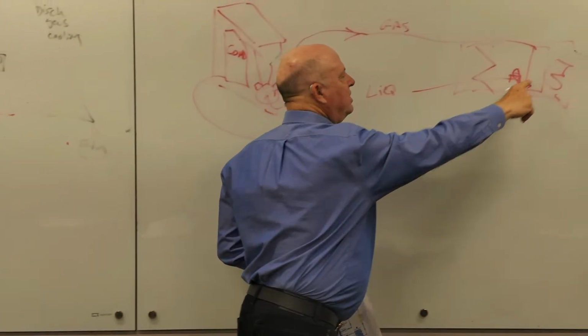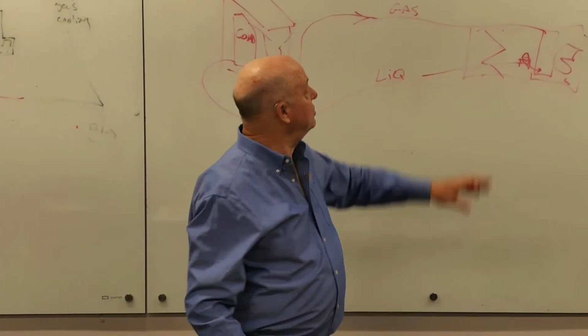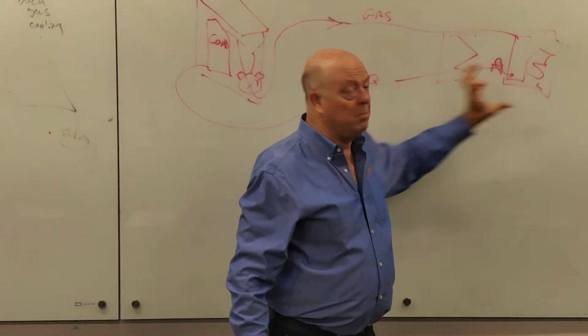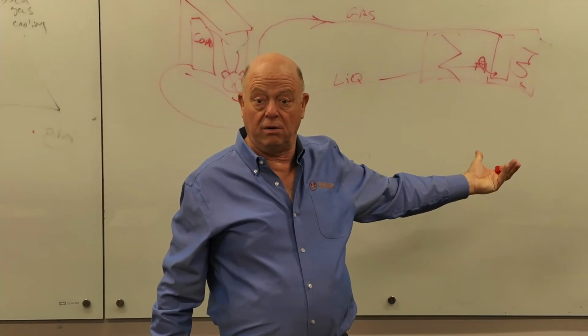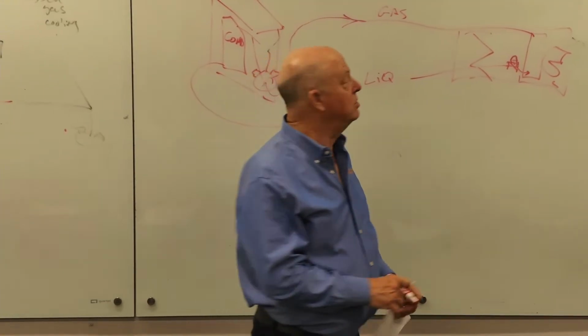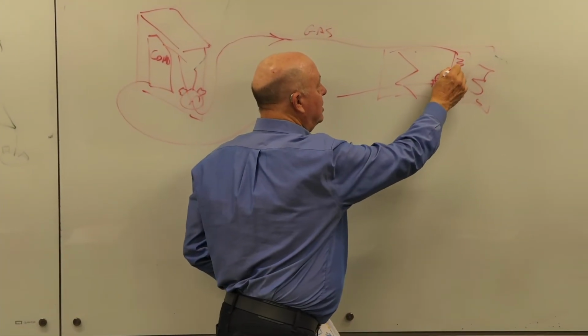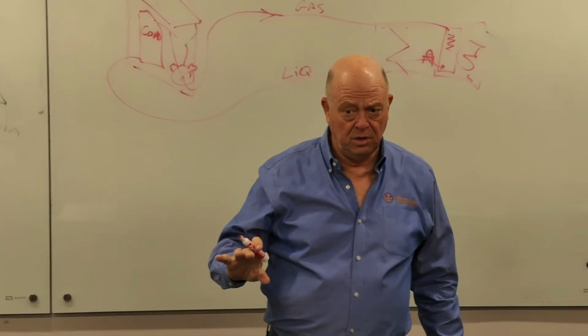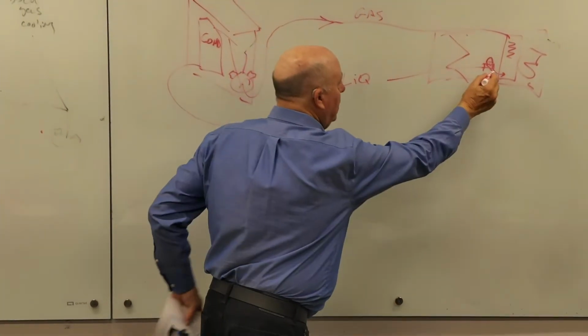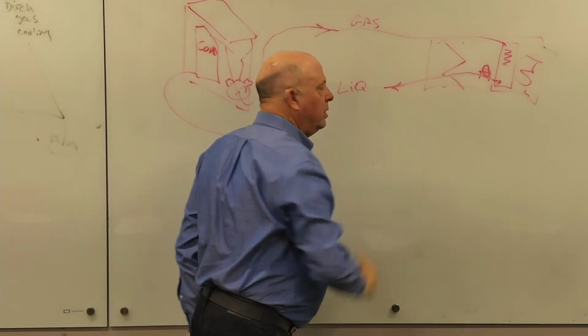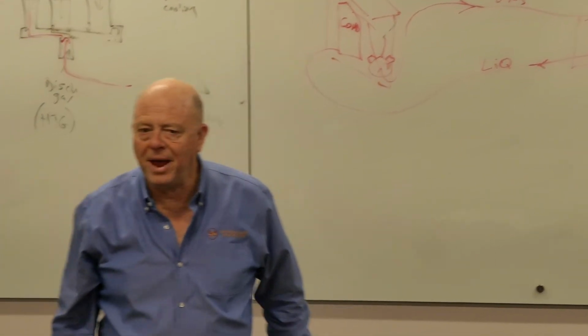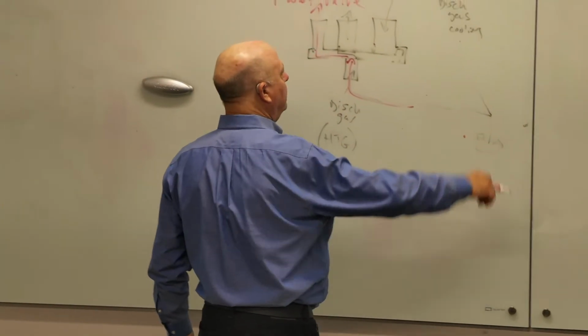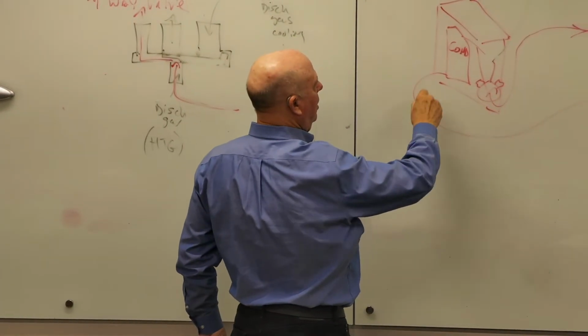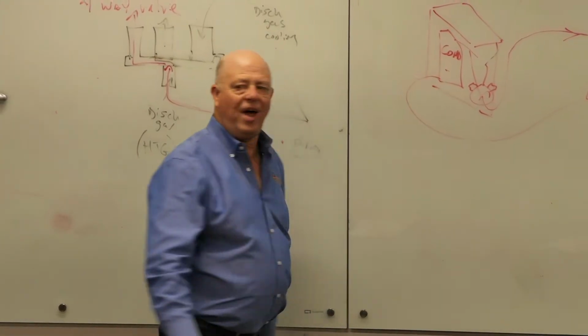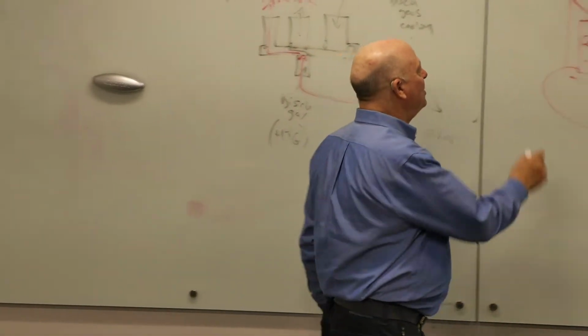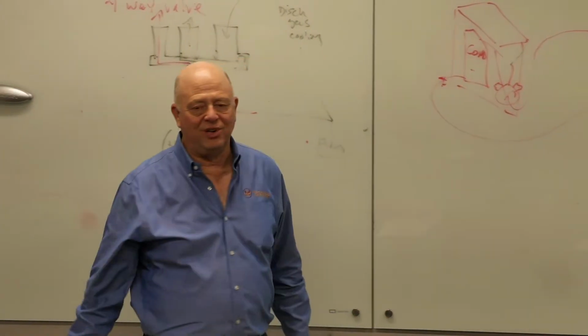And this is now our condenser. So if this is the condenser now, and we're putting the hot gas in there and we're blowing air across it, it heats the air, right? And that's what the heat pump does. And we've got to size this so it's got the right number of passes so that we'll get the proper liquid with a little subcooling coming back and to our condenser, which is now the evaporator, which means we need another expansion device.